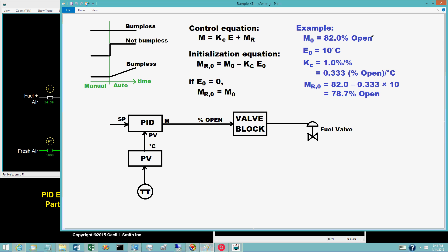The manual output is 82 percent open. The initialization calculations are: m sub r 0 equals 82.0 percent open minus 0.333 percent open per degree Celsius times 10 degrees Celsius, which gives 78.7 percent open. Neither the integral mode tuning coefficient nor the derivative mode tuning coefficient is used in the initialization calculations.